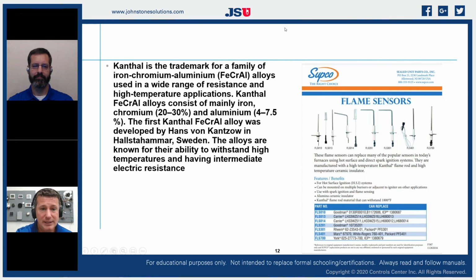So we do need to clean those, because they're not rated for 3500 degrees Fahrenheit. We do get some oxidation on those, because the metal is trying to protect itself from destruction, so it will oxidize on the surface, and then we need to actually clean those. Part of our maintenance procedure is to clean that flame rod or flame sensor to remove oxidation from it. We have to remove the surface that is actually burnt, because it's not rated to withstand 3500 degrees of combustion. It's rated for 1800 degrees of combustion.